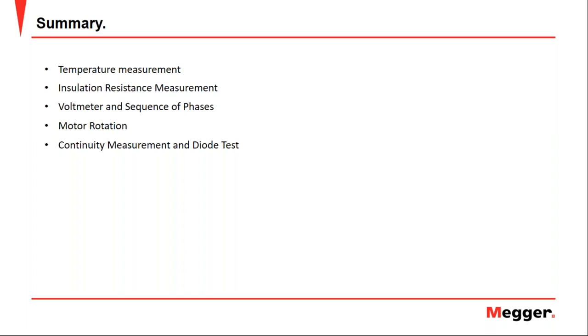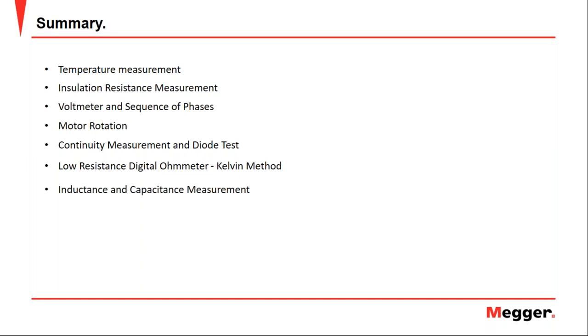We must perform the continuity test when the resistance measurement is in ohms. That is, for example, in small motors, and when we need a very accurate measurement in milliohms, we need to use the Kelvin method. The inductance and capacitance tests are only useful by trend. A single measurement of this variable is not enough to define the insulation system condition.